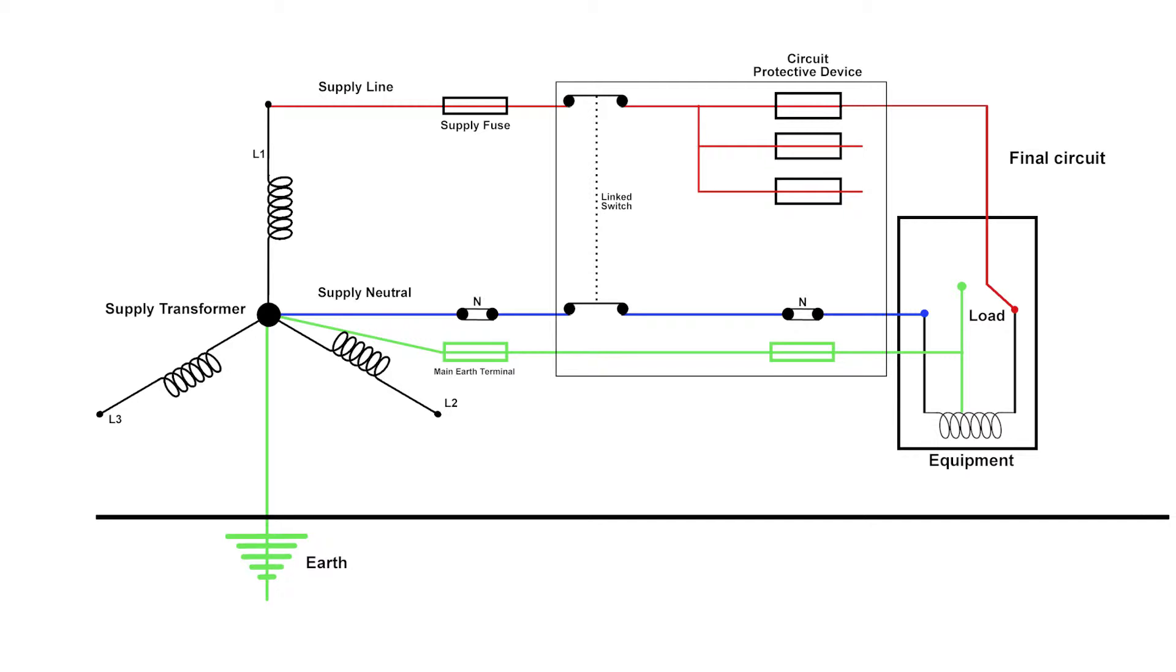Let's say that our circuit is supplying a three kilowatt load. If we do the calculations, we would know that a three kilowatt load is going to have a resistance of 17.69 ohms, which is 230 divided by 13 amps. If it's protected by, let's say, a 20 amp type B circuit breaker, we need to make sure that the circuit breaker is going to remain functional all the time the circuit is working. Obviously we've only got 13 amps flowing through the system and our circuit breaker is capable of withstanding 20 amps for quite a considerable period of time.